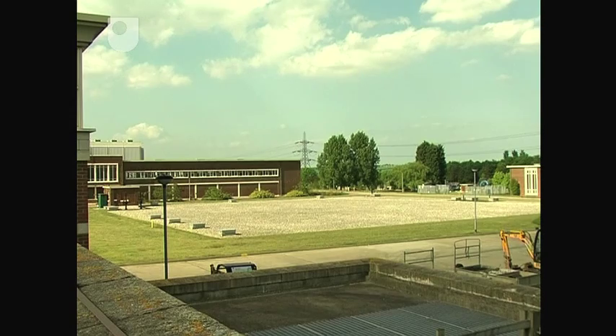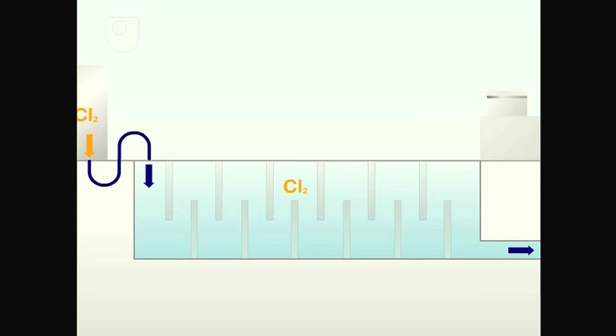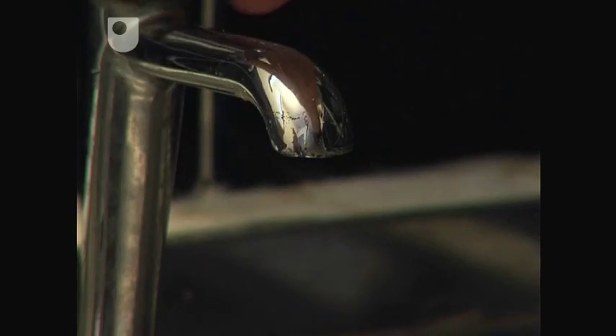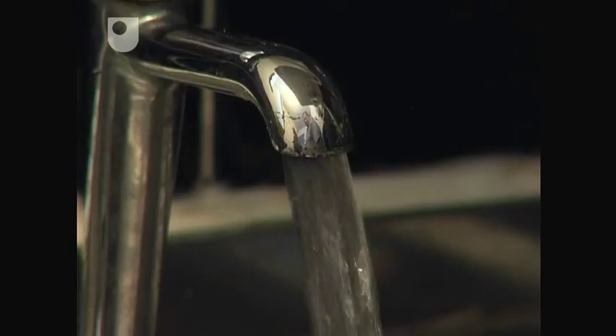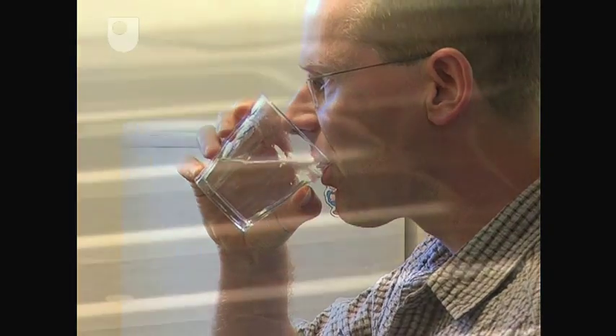And the final step occurs underground in a contact tank. Here the water is held for a carefully calculated residence time of about four hours to allow the chlorine to take effect. From the tank, it flows into the network of pipelines and service reservoirs en route to the consumer.